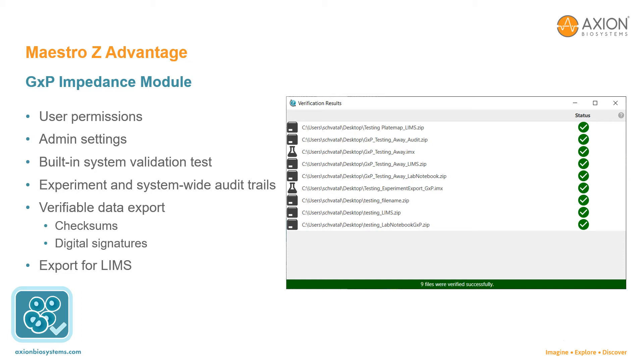The integrated barcode scanner ensures that all recorded data is associated with the correct plate, experiments are automatically sorted and logged, and events such as plate docking are auto tracked. Data and reports are exported with checksums and digital signatures to ensure data integrity, and it's easy to verify that experiment data has not been changed with a single click. CSV files can be exported for easy import into LIMS systems.